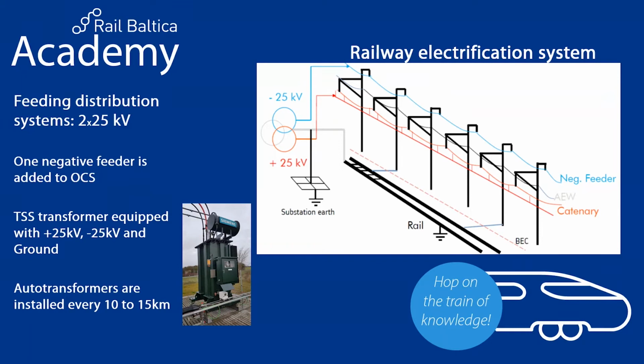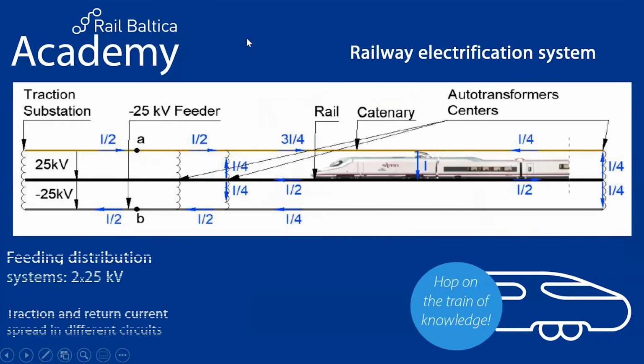The substation transformer is equipped with 3 connections: one is the ground, another is plus 25 kV, and the other is minus 25 kV - not a negative current, but alternating current in phase opposition. This is installed like this, and we will have auto-transformers implemented every 10 to 15 kilometers. So this is the structure of this 2x25 kV system, but we need to check this further.